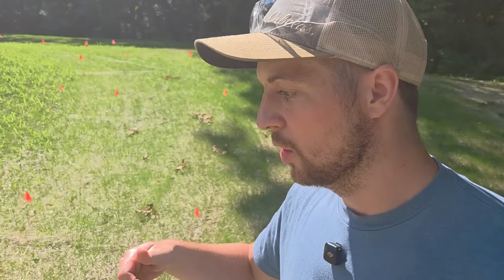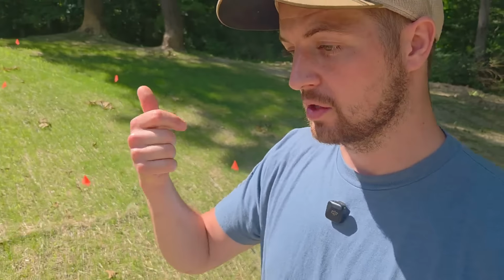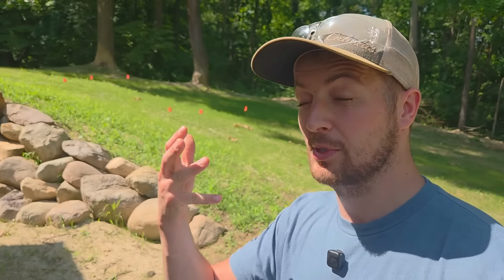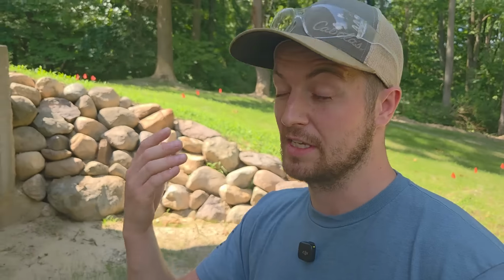That way I can measure what the water temperature is going in, how much the water temperature drops, what the air temperature is before it hits the heat exchanger, what the air temperature is when it leaves the heat exchanger, and what the temperature is at the heat exchanger of the water. I'm gonna get it all set up and let's see what we get out of it.